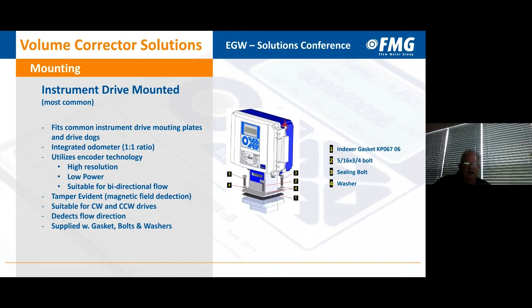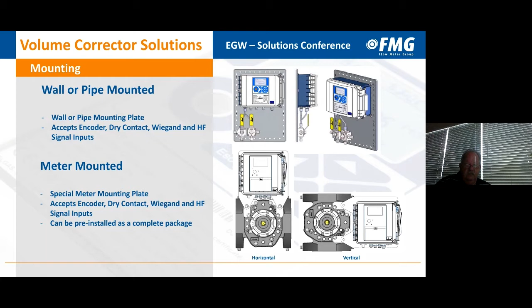The other way, and starting to see more and more every day, is wall and pipe mounting. So instead of using an instrument drive, you can use a pulse off of your meter to bring in to the corrector the volume passing through the meter. You can also pipe your pressure and then your temperature to the corrector, either as a wall mount, pipe mount, or even meter mounted now. So you don't have to have that instrument drive. Outside the United States, it is rare to find an electronic instrument attached to an instrument drive of the meter. They are typically wall mounted or pipe mounted. And in some countries, they do allow the meter mounting, but they do not rely on the mechanics of driving the volume on the corrector. They rely on a pulse coming out of the meter to the corrector itself.